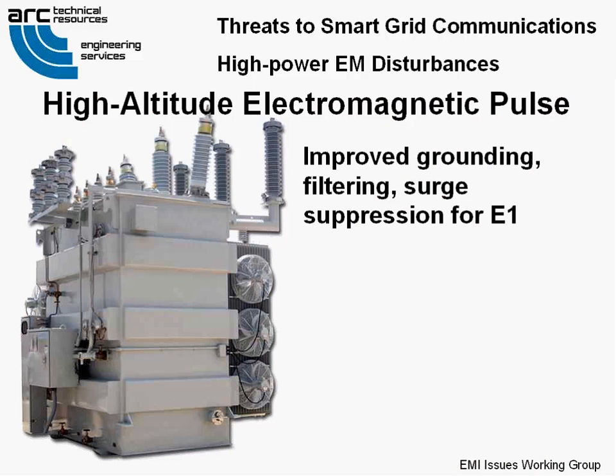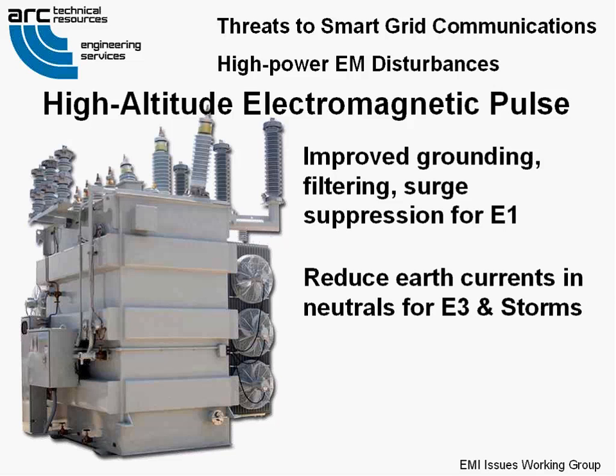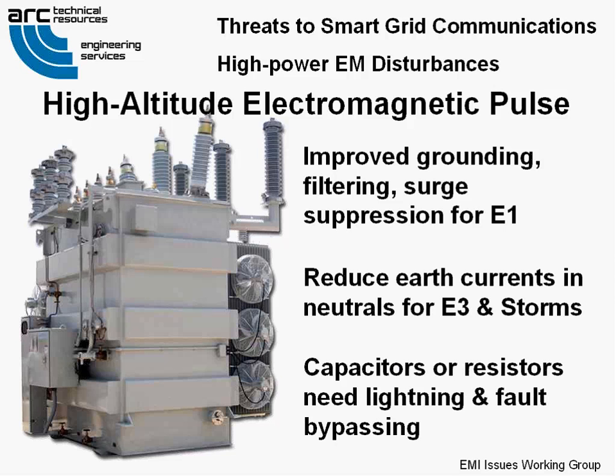For E3 low-frequency HEMP and extreme geomagnetic storms, the mitigation approach is to prevent or lessen the induced currents in the earth from coupling onto the grounded neutrals of the high-voltage transformers and substations. Neutral capacitors can block this current, and large resistors can reduce it, but fast bypass devices must be attached to either approach to allow lightning or fault currents to flow safely to ground without damaging the blocking device. These types of bypass devices have been successfully applied at lower transformer voltages than EHV, so similar techniques should work for EHV transformers. Product development and testing are required, along with standards development and field testing before deployment could begin, however. That high-speed bypass is normally in the form of a gas discharge tube.